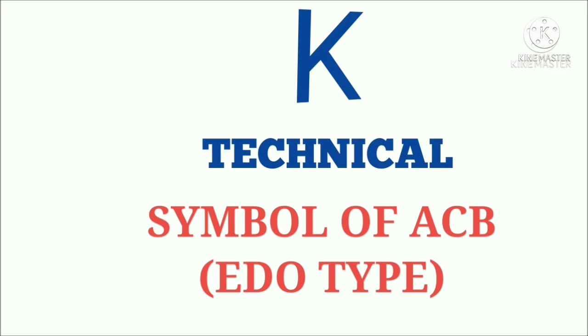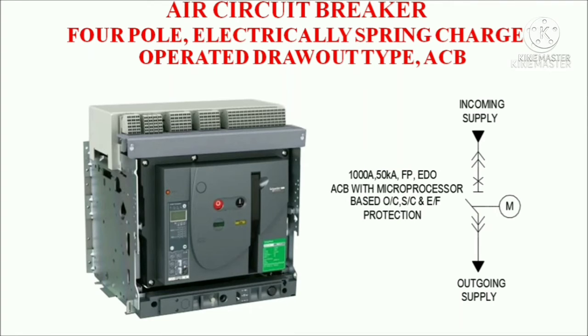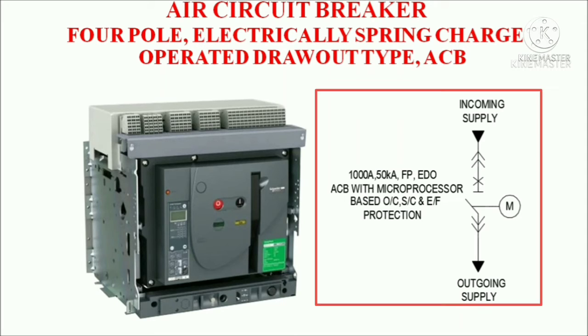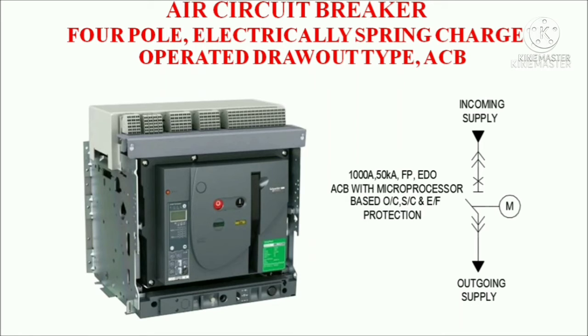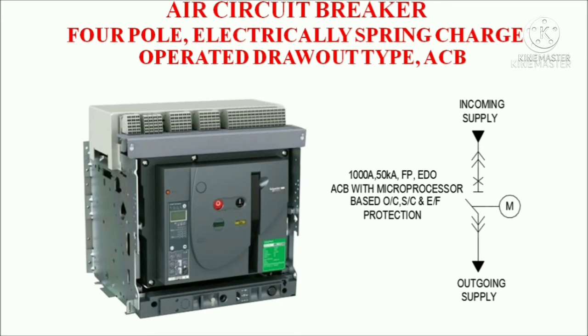Symbol of ACB EDO type. EDO type means spring charging will be done by motor, and the breaker is drawout type, meaning you can take the breaker out of the cradle. The symbol of EDO type ACB is shown here. For drawout, we use an arrow so that it is very clear whether it is EDO type or EF type.